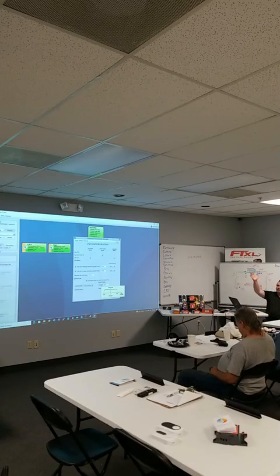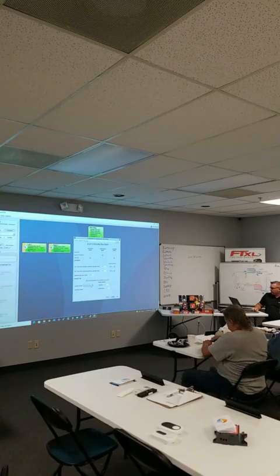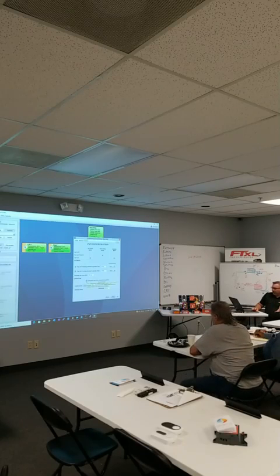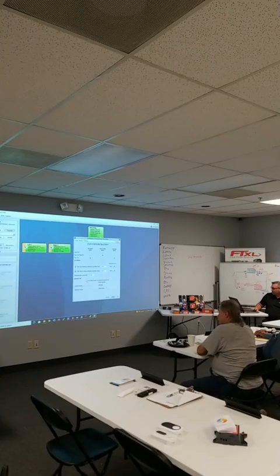It's going to drive open to 45%, kick on. It's going to have to swing down below 25 before it's going to turn off. And we just use that same standard hysteresis relay logic. Now, when you do choose that, if you wanted to use the digital output for W2, you wouldn't be able to, and it's going to tell you that. So I'm just going to disable it for now.